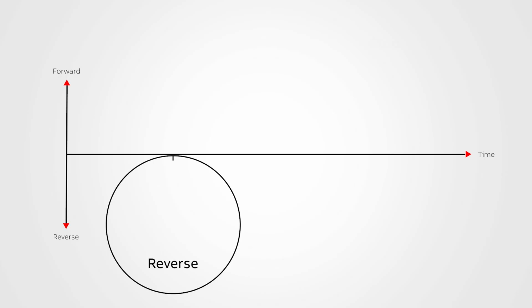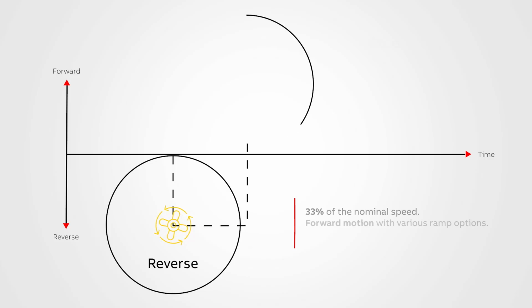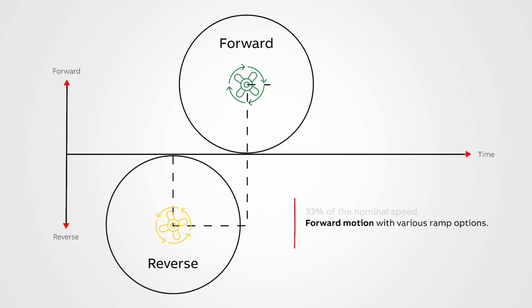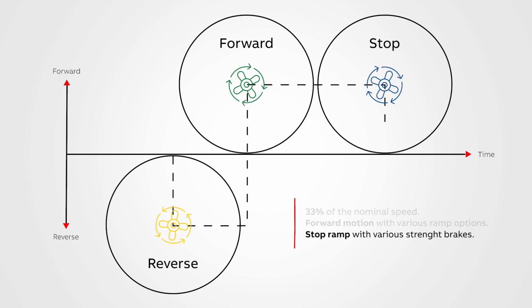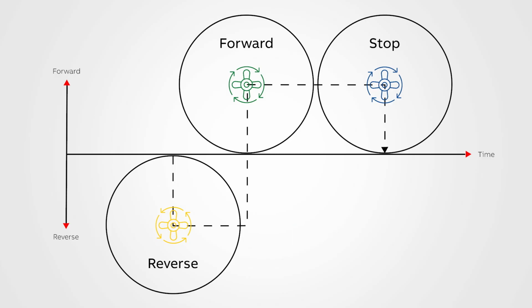The cleaning sequence. During a cleaning period, there are 3 distinct sequences. The first sequence commences with a reverse jog, which is limited to a maximum of 33% of the nominal speed. This is followed by a forward motion, which offers various ramp options. The sequence concludes with a stop ramp, which incorporates brakes with varying strengths. The intensity of the cleaning can be adjusted, but stronger cleaning may pose a greater risk to the system. In the next part, we'll explore the things we need to tweak.